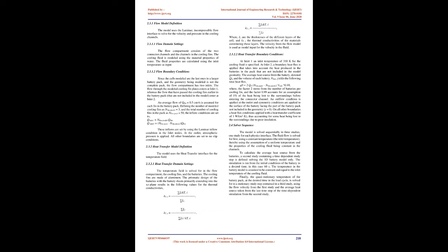An average flow per fin equal to 0.5 cm/s is assumed for each fin in the battery pack. Defining the number of modeled cooling fins as N_fins_model = 3, and the total number of cooling fins in the pack as N_fins_pack = 50, the inflow conditions are set: Q_inlet1 = N_fins_model times the fin flow, and Q_inlet2 = (N_fins_pack minus N_fins_model) times the fin flow. These inflows are set using the laminar inflow condition at the inlet nodes. At the outlet, atmospheric pressure is applied. All other boundaries are set to no-slip conditions.